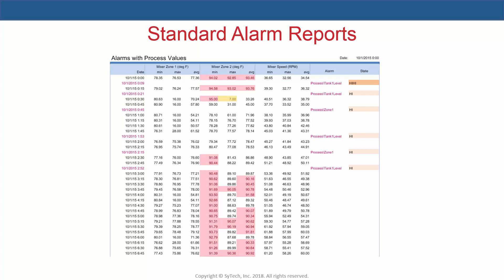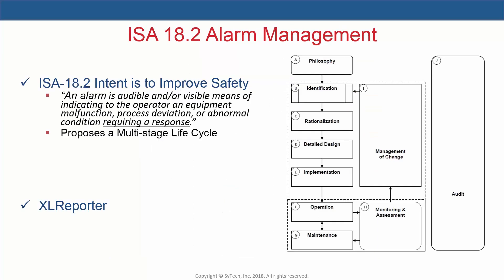All of these reports provide useful information about the alarm system, but we'll now turn our attention towards reporting for ISA compliance. The ISA 18.2 standard is considered a recommended and generally accepted good engineering practice by regulatory and insurance agencies, and aims to increase safety and optimize operator response to alarms. It proposes a multi-stage life cycle based around continually monitoring and improving alarm system performance. SyTech provides a benchmark report useful for control engineers and system integrators looking to evaluate alarm system performance against ISA standards.